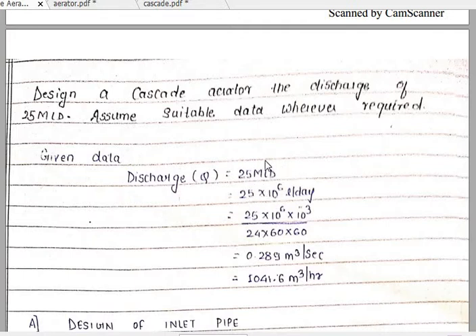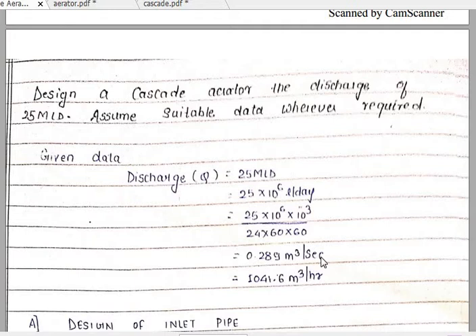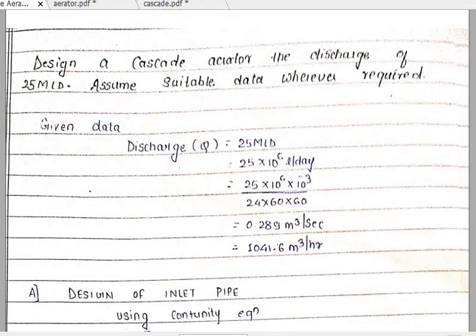This is the conversion factor involved in various numericals — the discharge will always be given in million liters per day and you have to convert that value into meter cube per second or meter cube per hour. Since the design criteria are given in meter cube per hour, we need both values. By dividing only by 24 instead of 24 into 60 into 60, we get Q equal to 1041.6 meter cube per hour. Now the first step is the design of the inlet pipe.